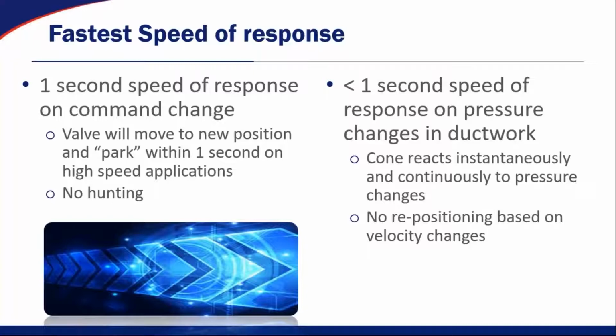Secondary to that is the 1 second speed of response on pressure changes in the ductwork. And going back to the beginning of this presentation, when we talked about that pressure independent cone with the spring in it, that's what we're referring to, 1 second speed of response to changes in ductwork pressure. So basically, individually or separately from the control platform that's telling the valve where to go, that cone, that mechanical spring inside of the cone, is actually repositioning itself in real time to make sure whatever set point the valve is set at, you're going to get your airflow within plus or minus 5%.